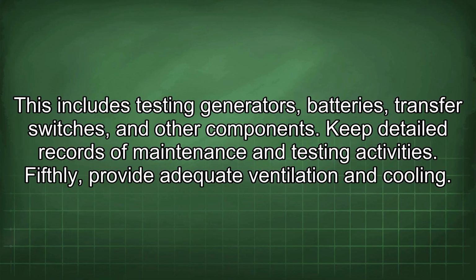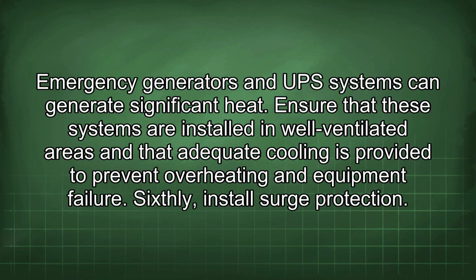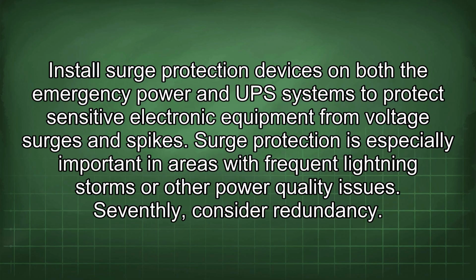Fifthly, provide adequate ventilation and cooling. Emergency generators and UPS systems can generate significant heat. Ensure that these systems are installed in well-ventilated areas and that adequate cooling is provided to prevent overheating and equipment failure. Sixthly, install surge protection. Install surge protection devices on both the emergency power and UPS systems to protect sensitive electronic equipment from voltage surges and spikes. Surge protection is especially important in areas with frequent lightning storms or other power quality issues.